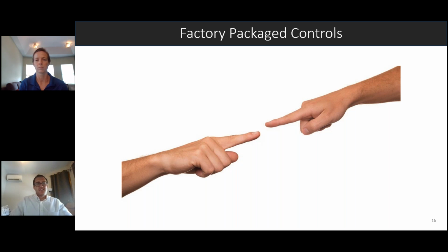Another big thing that's in the specs, or should be in the specs, is your wiring requirement. And like I said, wiring can be anywhere from 30 to 70% of your cost. So you really do need to know whether or not you're supposed to be running the entire job in conduit or not. That could be a big game changer in your pricing.